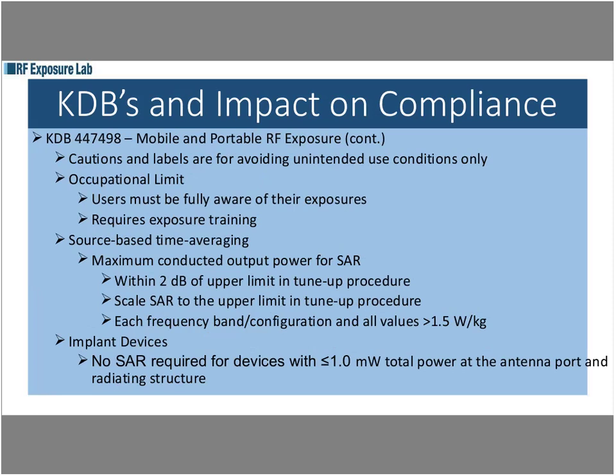And then here I'm going over cautions and labels, which are for avoiding unintended use conditions only. You can't use a caution or a label to tell someone not to do something in order to get out of meeting SAR, by saying, oh, don't hold that cell phone closer than 5 centimeters from your body. The FCC doesn't allow that. You have to do the testing in what normal use operation would be, and you have to pass at that level. You can't use any kind of cautions or labels to get out of SAR testing.